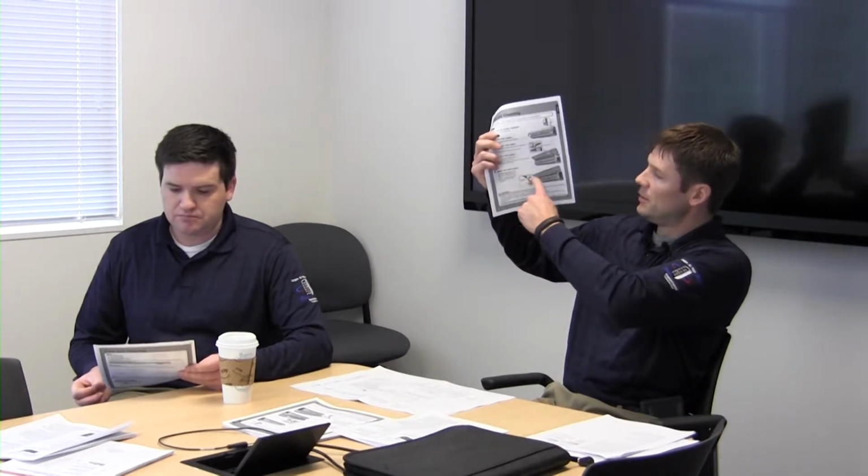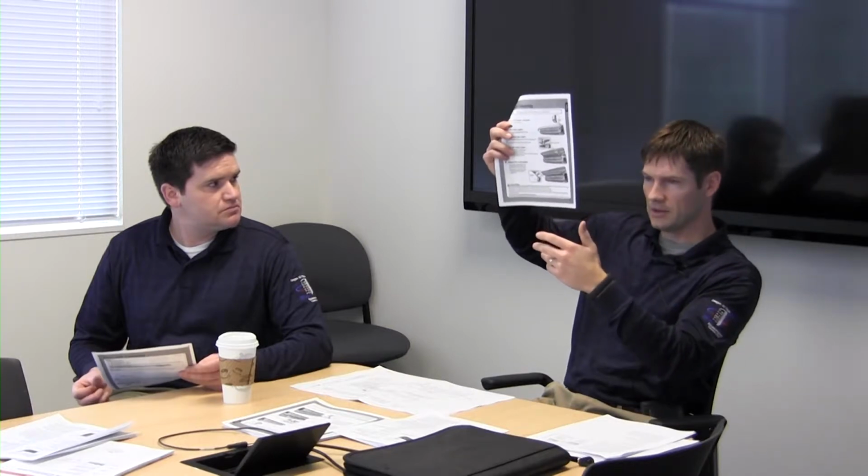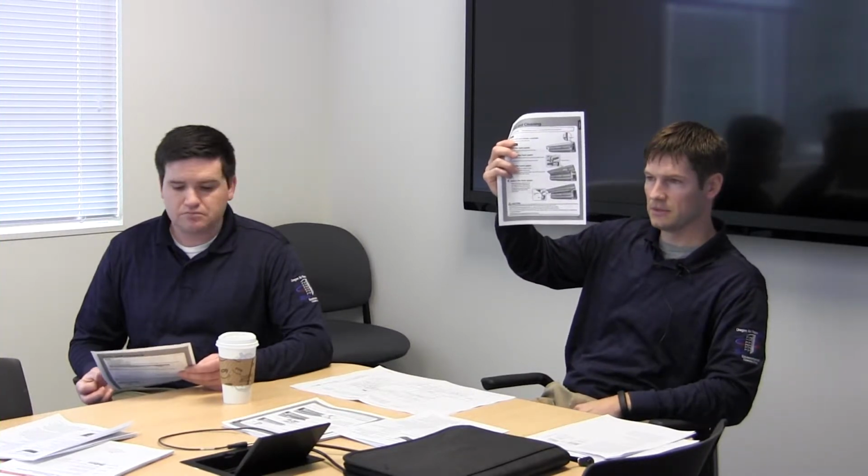The next unit is the split system. Mini split system is usually what they're called. And this one is a 3-ton. It's about the biggest you can get and still be of this type. It's got an indoor unit, which looks like this. It's a long, skinny unit that hangs on the wall. Behind that, in the wall, you have your refrigerant connections, two refrigerant connections that go out to the outdoor unit that's up on the roof.